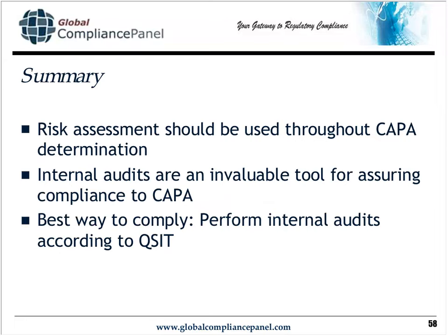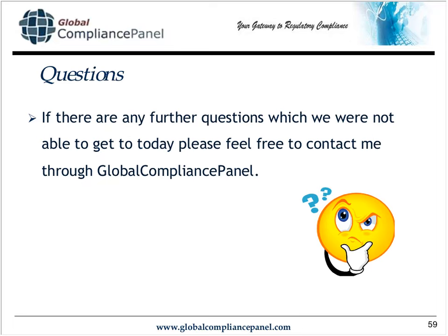And last, the best way to comply with this is to restructure your internal audit program so that instead of auditing to maybe the ISO standard format-wise, you audit according to QSIT. This way, you are already asking the questions that you know that you and your people know the inspector will ask, and it gives you a lot of good practice. So that's the end of the webinar, and I'll turn it back to the moderator to solicit Q&A.